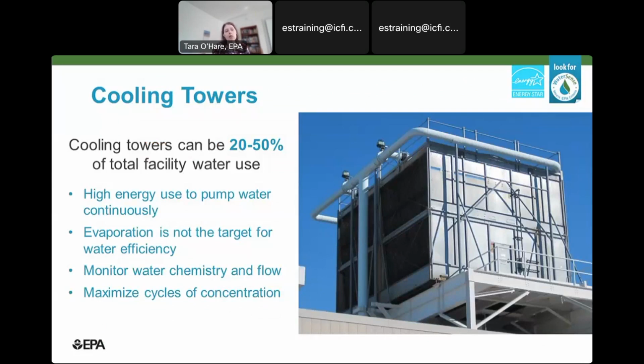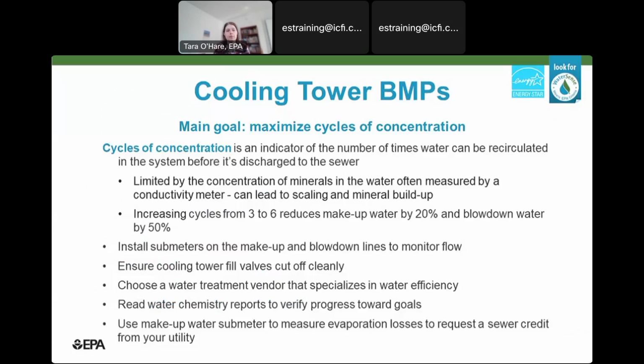And one thing to keep in mind is that the whole point of a cooling tower is to evaporate the water to remove the heat load. So we're not targeting evaporation for water savings. We want that to happen. So we don't want to target that in our water savings efforts. You can monitor water chemistry and flow and maximize cycles of concentration. So cycles of concentration is an indicator of the number of times that water can be recirculated in the system before it's discharged to the sewer.